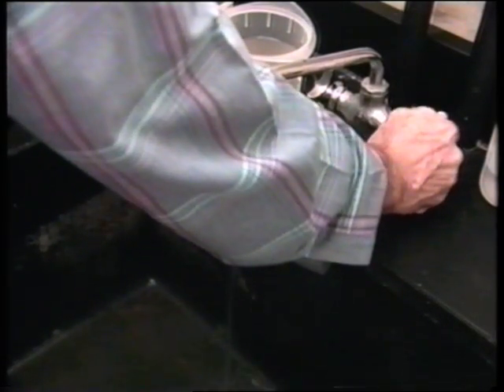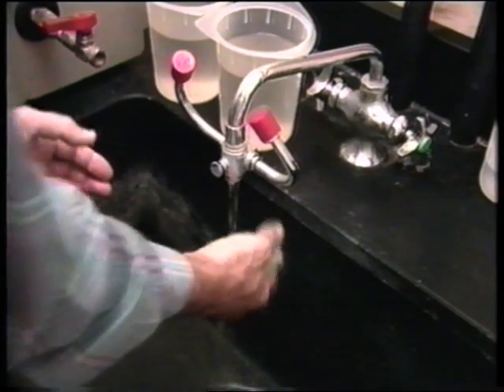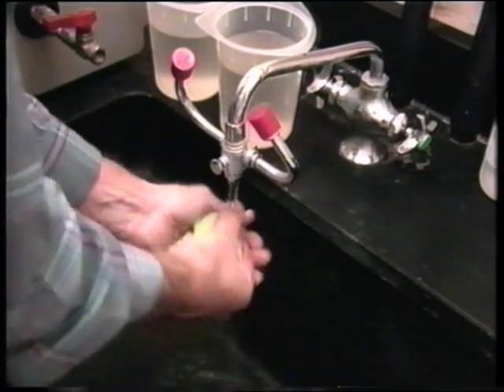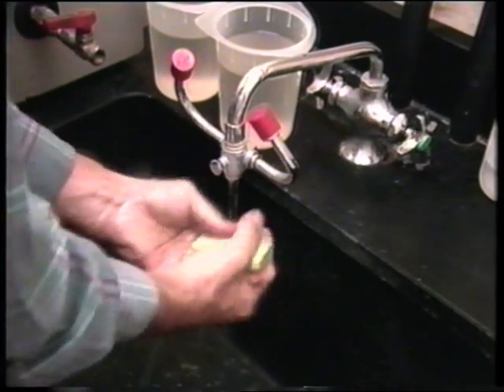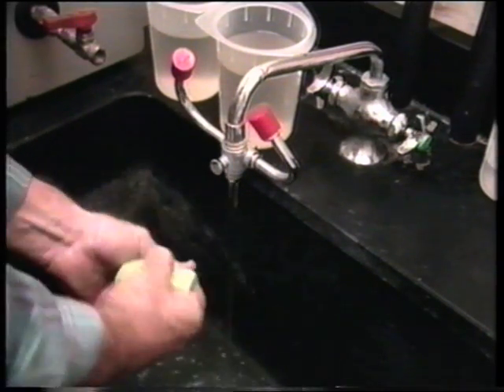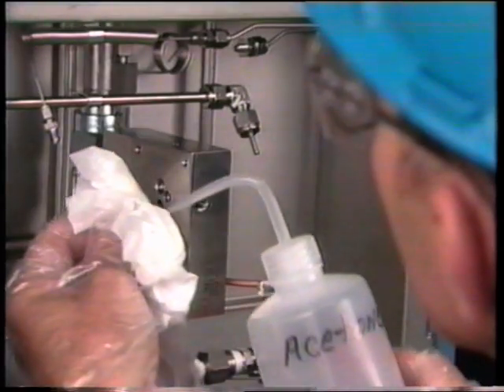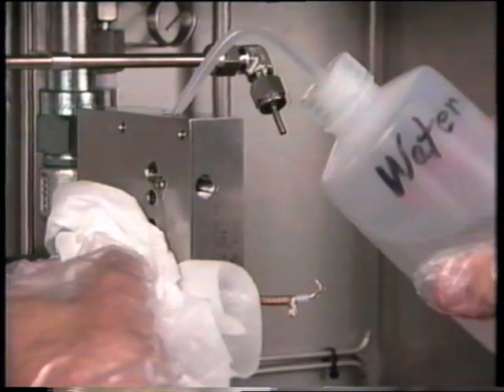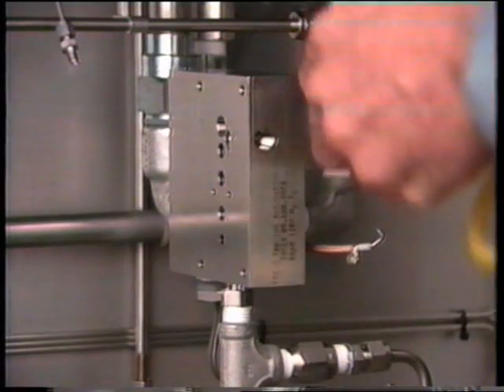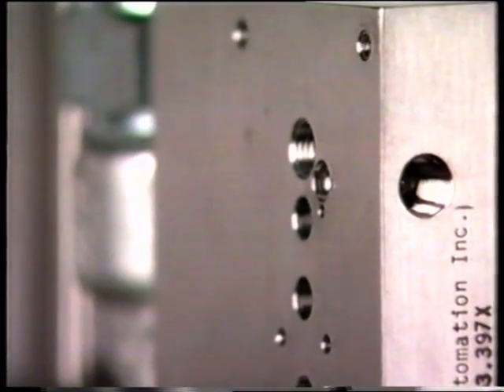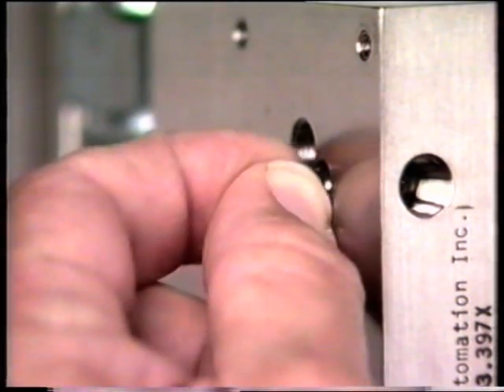Avoid excessive touching of any of the parts from the sensor side of the detector. Extremely sensitive applications may require the use of protective gloves to handle the detector pieces. Now, use solvent to clean the detector block, then flush it with distilled water and blow dry it with low-pressure air. After all the pieces of the detector have been cleaned, it can be reassembled.